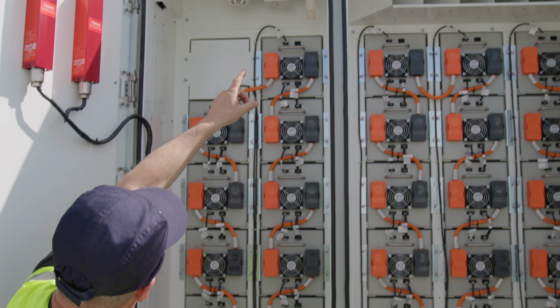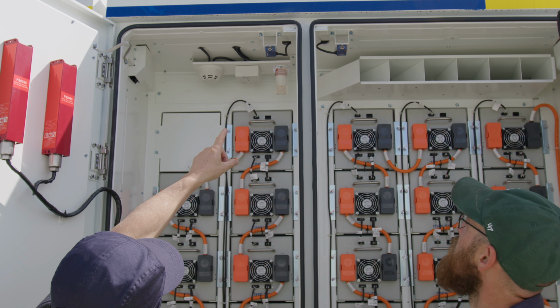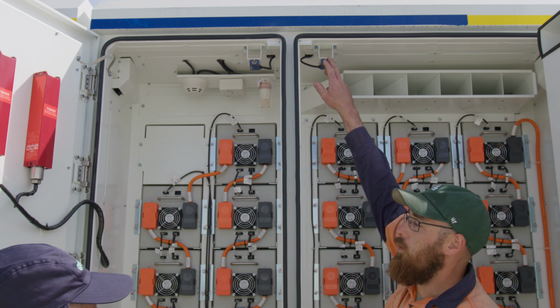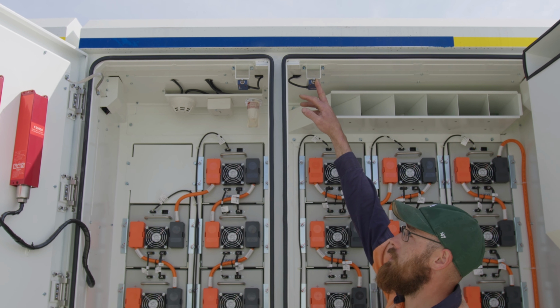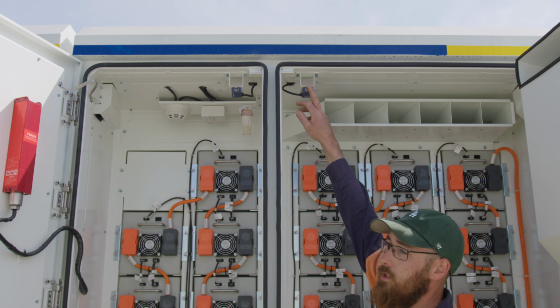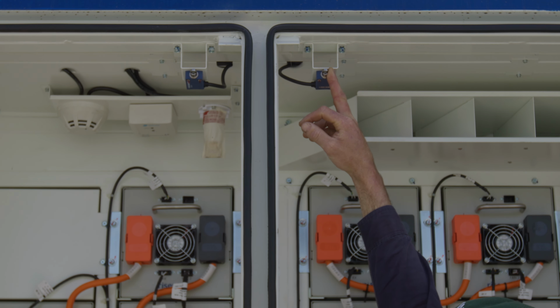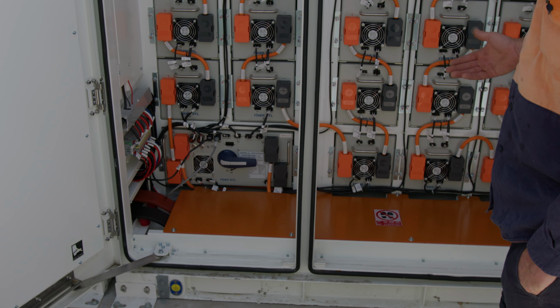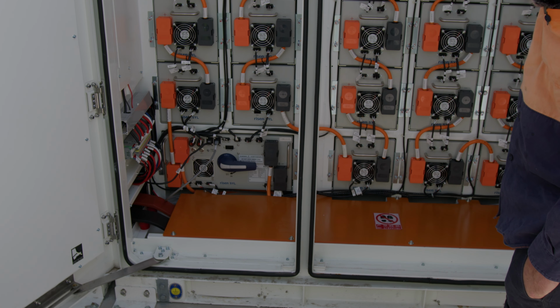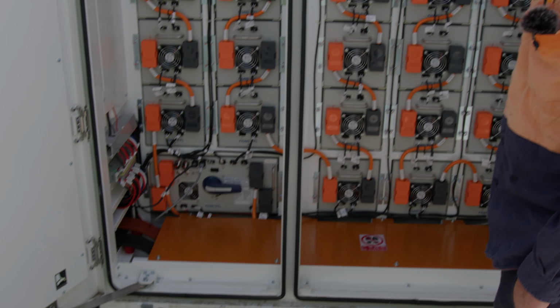Is this some kind of door sensor thing? Yeah. So all of the battery connection panels and the batteries themselves have these door switches. So if any of the doors are opened, it'll de-energize the system immediately. Likewise, if there was an explosion in here, it'll push the doors off their hinges, which would disconnect everything.